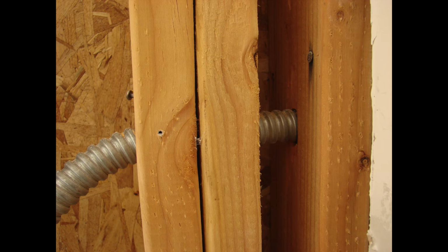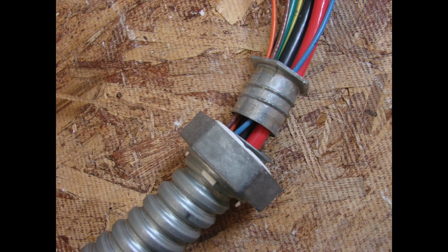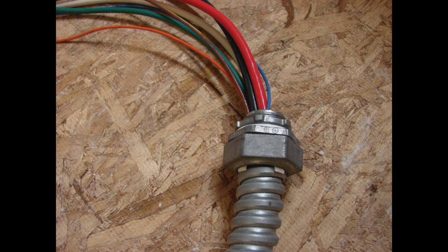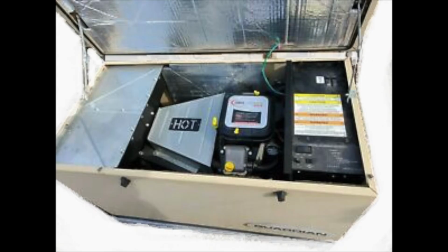So we've pre-drilled the holes in these studs, and we're running the SER cable and the flex cable. The SER cable, again, service entrance rated cable, goes to the main panel, and a junction box, which we'll see, where we're going to be intercepting the other sub panel and splicing that outside of the main panel. The flex for the generator will be routed through the holes in the studs here and then poked out the side of the wall to the generator itself. And we're looking at the generator itself. We're opening that up. With any generator that you get, you're going to have an accessible enclosure.